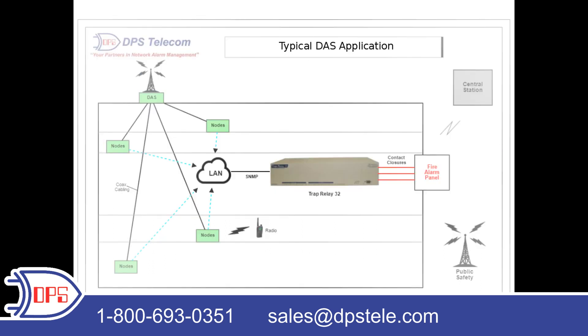The third common application is using our trap relay for the fire department. They have a distributed alarm system, or DAS, that outputs SNMP. They need to feed this into their fire panel, which only accepts contact closures. With the trap relay, they'll send SNMP via LAN directly to the trap relay. The trap relay then converts SNMP to contact closures via relay output that can tie into the fire panel. The Trap Relay 32 and 64 are our most common units. We also have smaller variations like the Trap Relay 4 and Trap Relay 8 available as well.